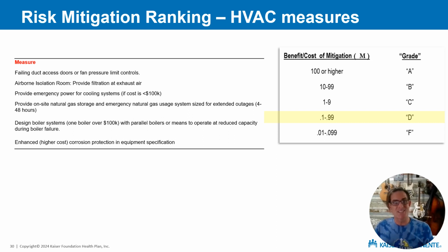right? So these are the D's where the benefit that we could potentially get out of the investment is an order of magnitude less than the investment that we have to put in. And I'll have you notice that there are some code requirements here, some very common things that we do in hospitals that fall into this category. In California, we're actually required to put filtration at the exhaust of airborne isolation rooms. That is not a good cost benefit. Providing emergency power for cooling systems, not a good investment. You'll also see about fourth on the list, some on-site fuel storage, up for moderate outages, up to 2 days. That's at this D level.